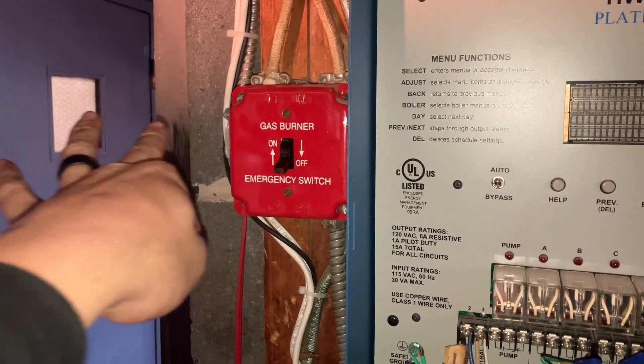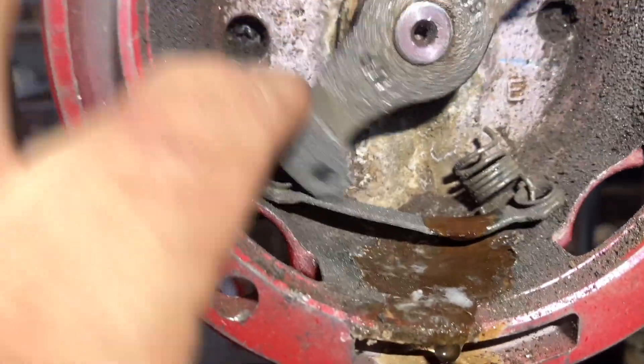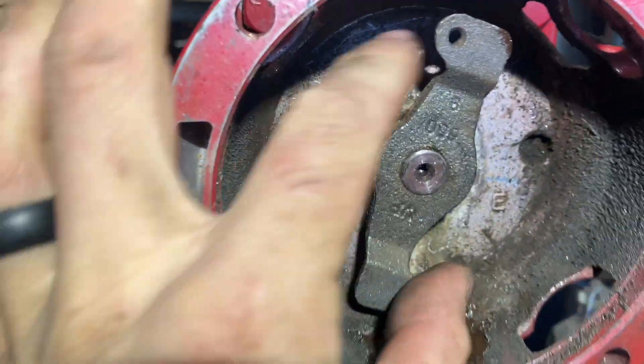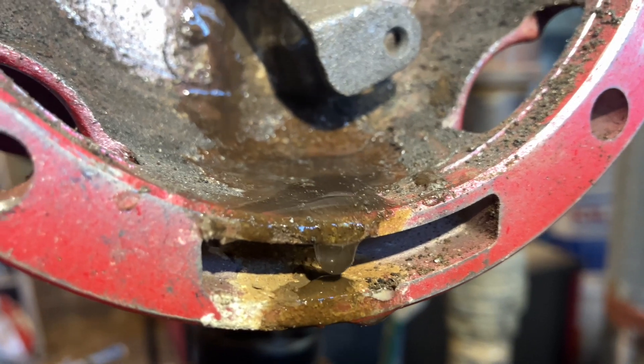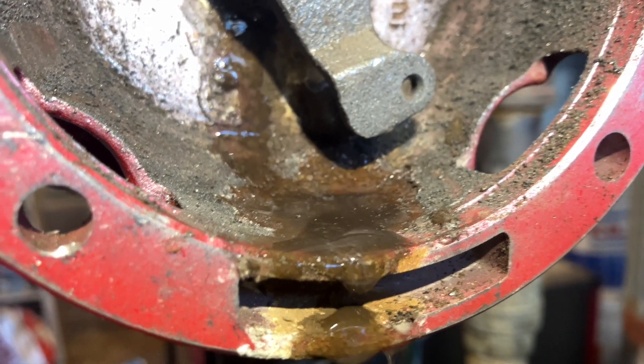Spoiler off for now. The bearing's starting to leak. I mean, it spins, but... Looks like it's been swapped out once before. Not a knock on B&G, though. Probably just opened Pandora's box doing that.